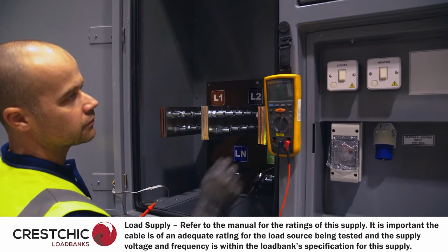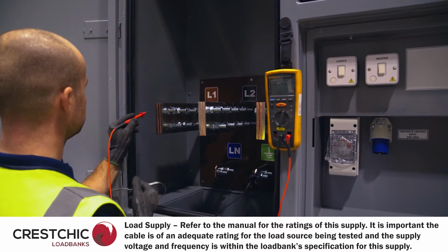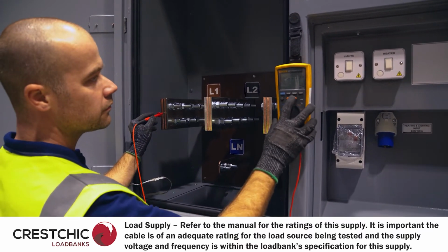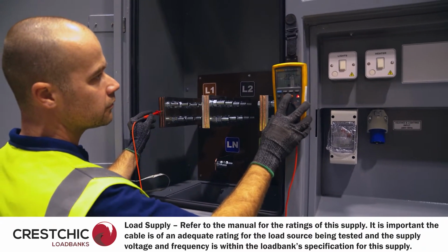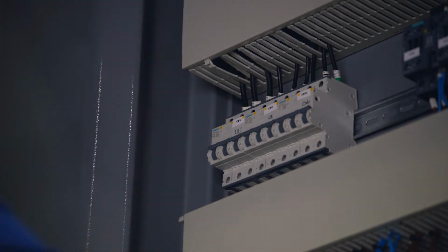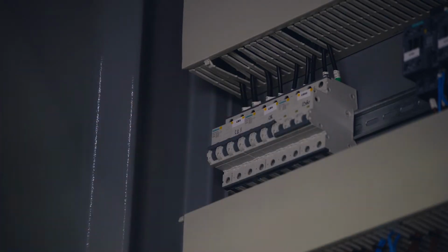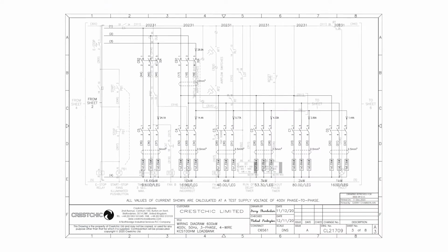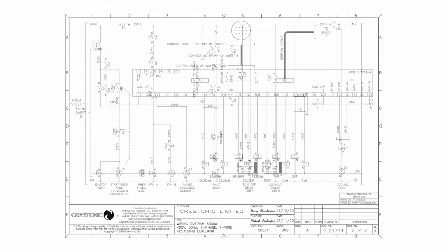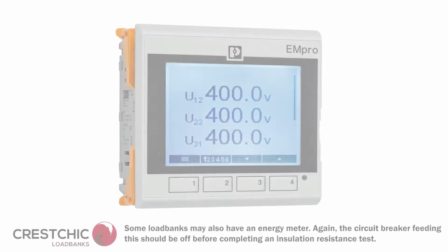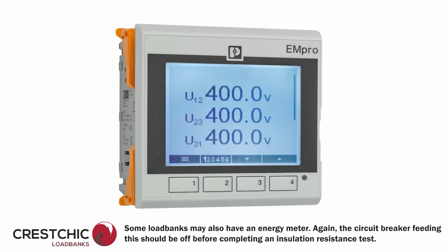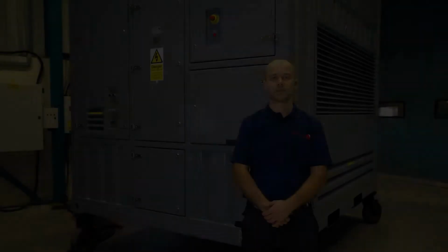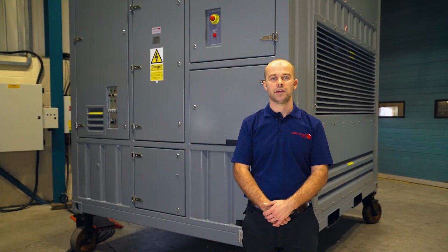Please note, when completing an insulation resistance test on the load supply, the load bank's transducer should be isolated. This is typically done by switching off the circuit breaker feeding this transducer, referring to the wiring diagrams to check which circuit breaker this is. Some load banks may also have an energy meter. Again, the circuit breaker feeding this should be off before completing an insulation resistance test. Please refer to the manual for further information.